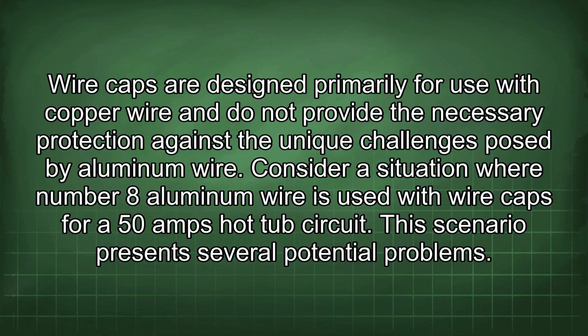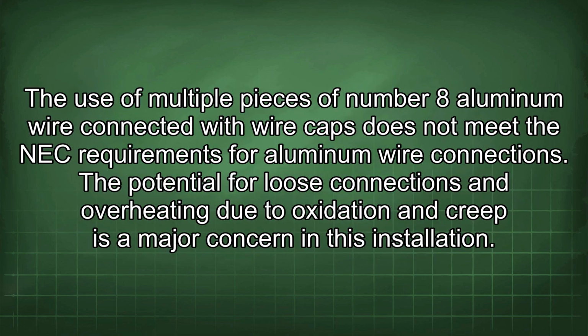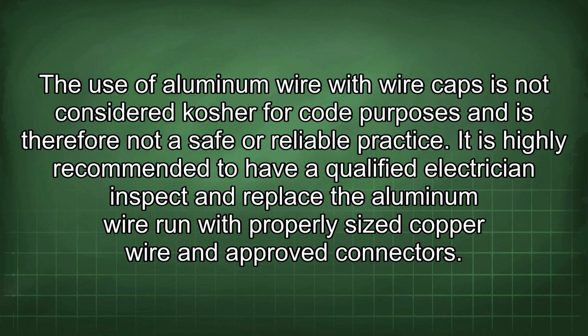Consider a situation where number 8 aluminum wire is used with wire caps for a 50 amps hot tub circuit. This scenario presents several potential problems. The use of multiple pieces of number 8 aluminum wire connected with wire caps does not meet the NEC requirements for aluminum wire connections. The potential for loose connections and overheating due to oxidation and creep is a major concern in this installation. The use of aluminum wire with wire caps is not considered kosher for code purposes and is therefore not a safe or reliable practice.